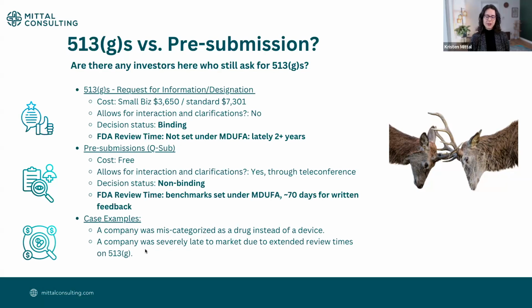The decision status: all correspondence you have back and forth here is non-binding. It's only recommendations from the FDA, although you should follow their recommendations. And then the FDA review time for this is set under MDUFA to about 70 days for the written feedback. So they do, in general, try to review most of them within approximately 70 days and provide that written feedback. So maybe not so common in the US, but we have a lot of our European colleagues file first for the 513(g) as opposed to going through the pre-submission in order to determine what their regulatory pathway is.